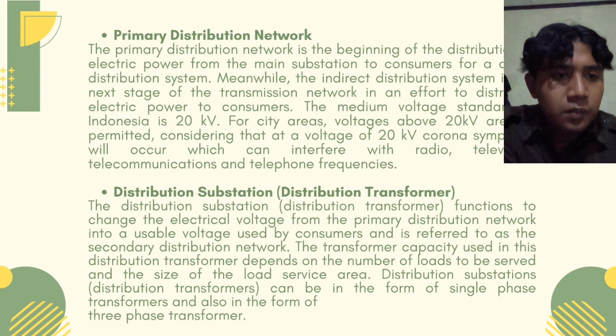Distribution substation. The distribution substation functions to change the electrical voltage from the primary distribution network into a usable voltage used by consumers, referred to as the secondary distribution network. The transformer capacity used in this distribution transformer depends on the number of loads to be served and the size of the load service area. Distribution substations can be in the form of single phase transformers and also three phase transformers.